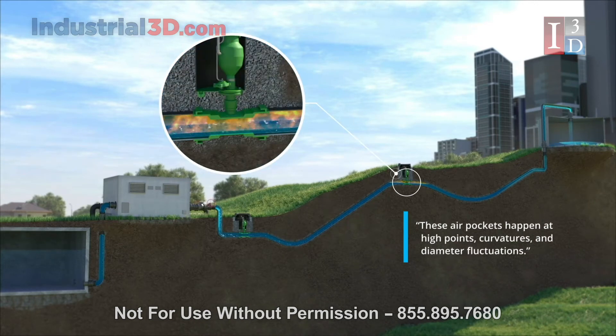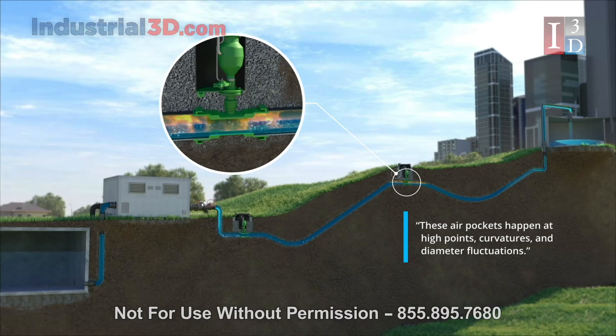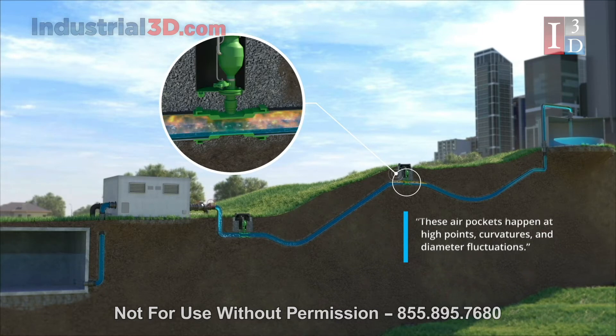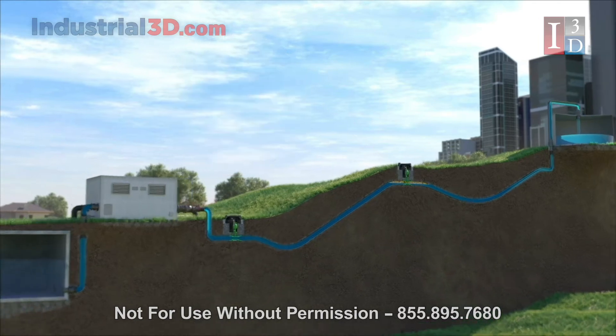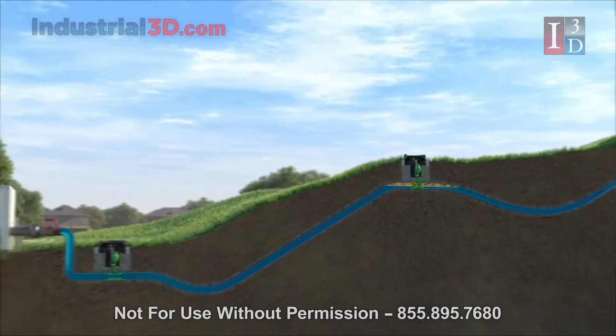Notice at the high point there is an accumulation of air and corrosive gases. Without an air valve, these pockets would create a reduction of flow, stress the pipe, and accelerate the corrosion process.